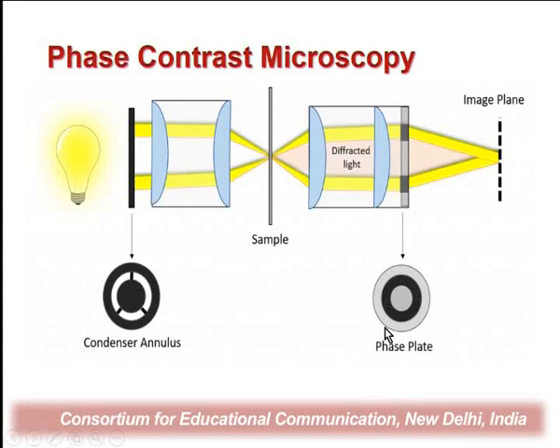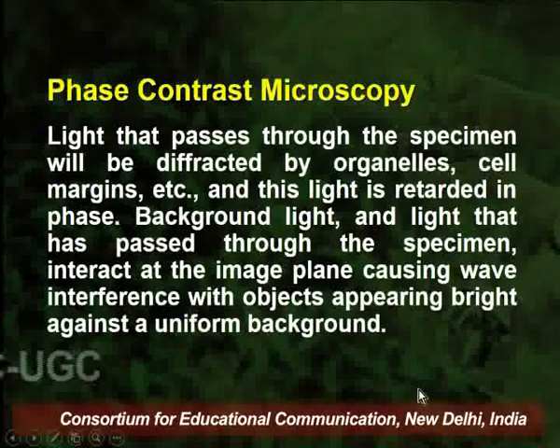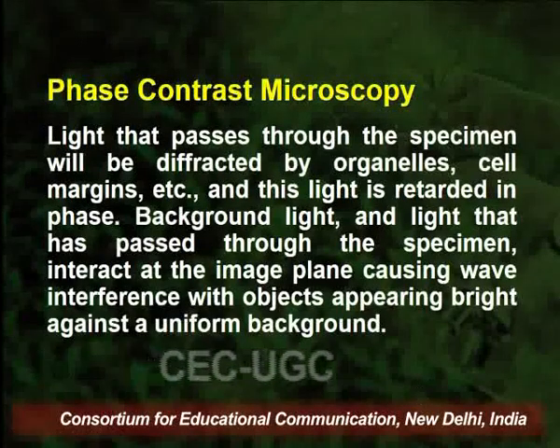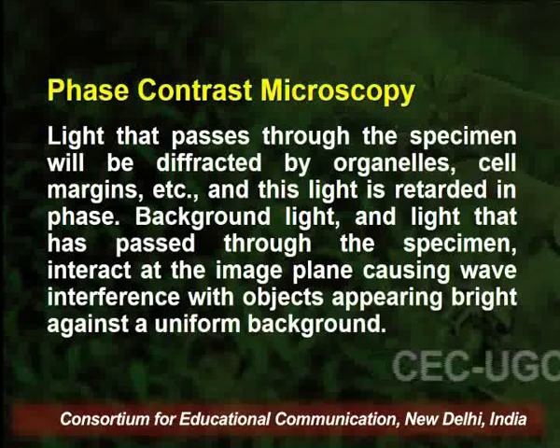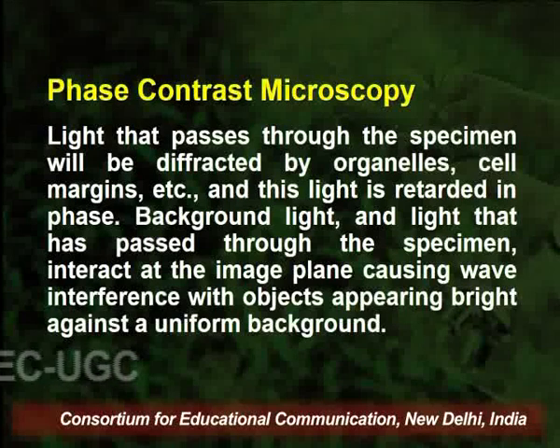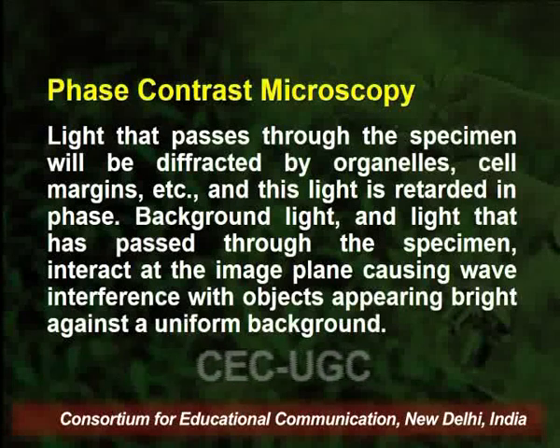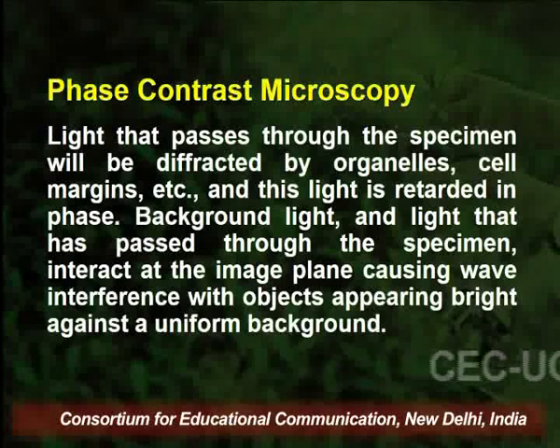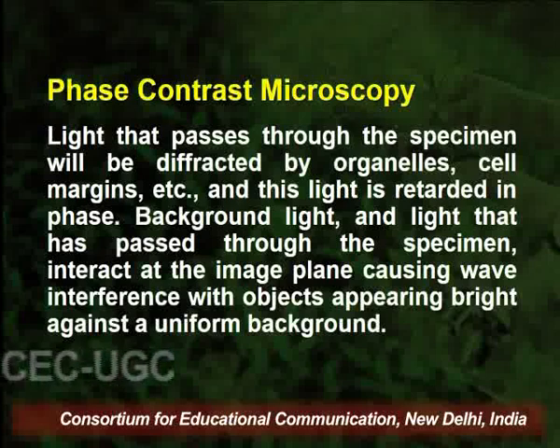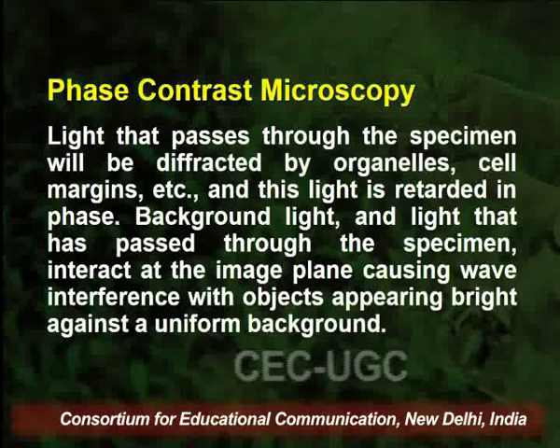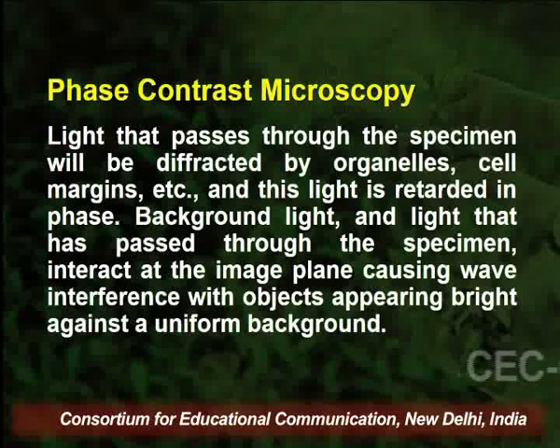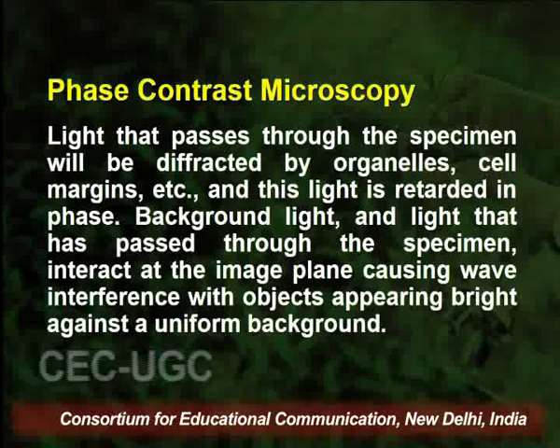Because of the presence of the phase plate, objects differ in their brightness and darkness, and this change in brightness and darkness creates a greater contrast at the image plane. In short, the light that passes through the specimen will be diffracted by organelles, cell margins, etc., and this light is retarded in phase. The background light and the transmitted light interact at the image plane causing wave interference, with objects appearing bright against a uniform dark background.